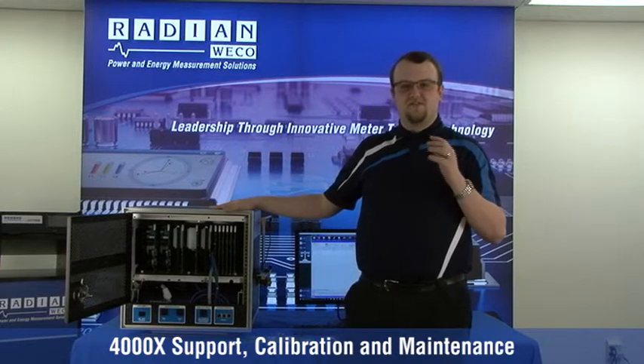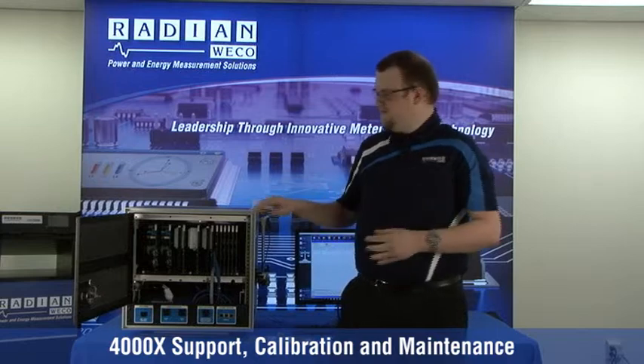It's that simple. As a good practice, we would recommend running a standards compare on the test board after any card replacements. The standards compare process will verify that the test board can generate at all specified voltage and current levels, as well as verifying the accuracy of the internal reference standard.